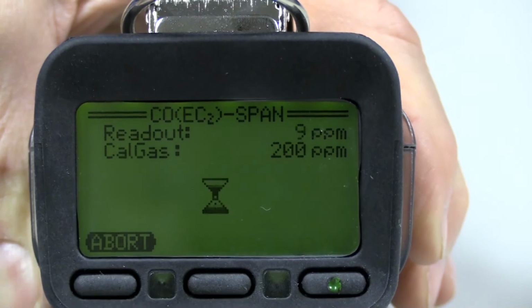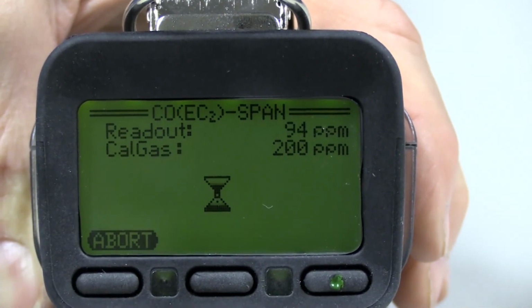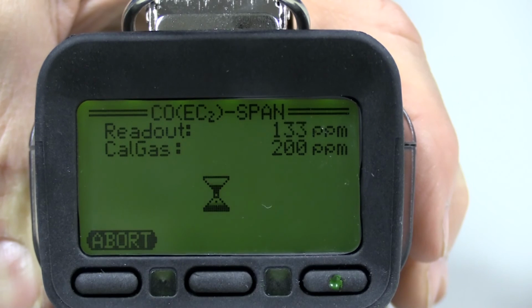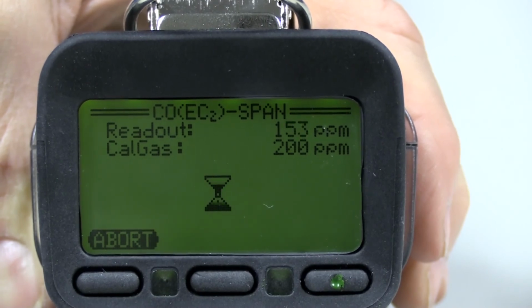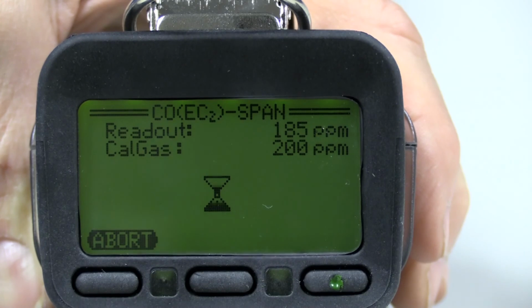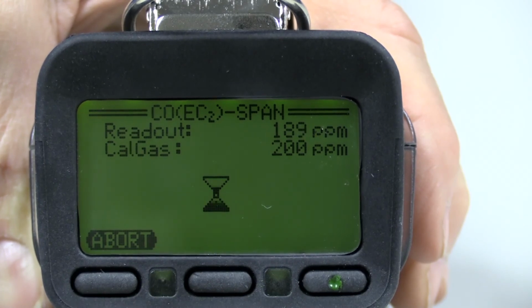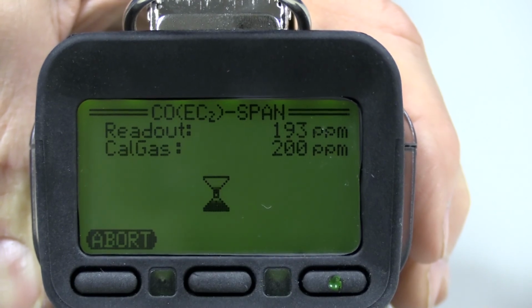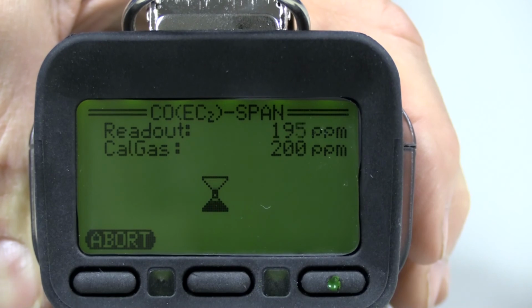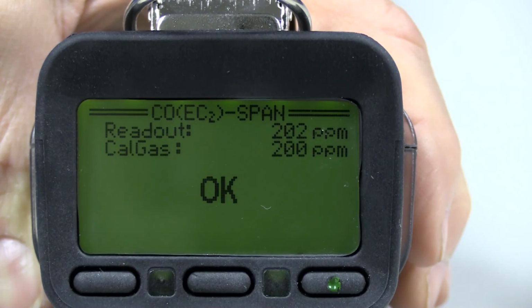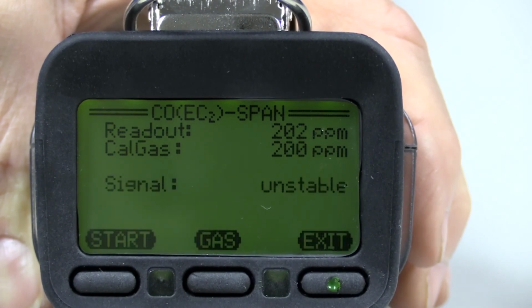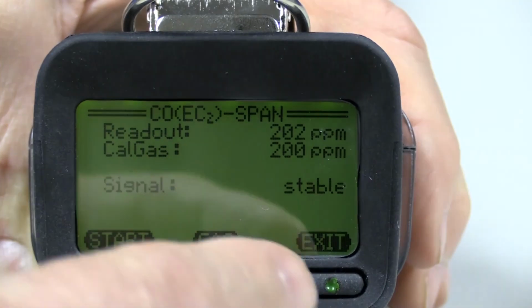If you take a little bit too long with these steps, the instrument may time out and return to normal operation. If this happens, leave the fittings attached, re-enter the service menu, and return to the Calibrate screen and press Start. The screen will show you the current reading and the concentration of gas being used to adjust the sensor. An hourglass icon will show in the display while the sensor is being adjusted. After the adjustment is complete, the display will briefly show an OK message, then go back to showing the Calibrate screen. The gas reading should now match the gas concentration.